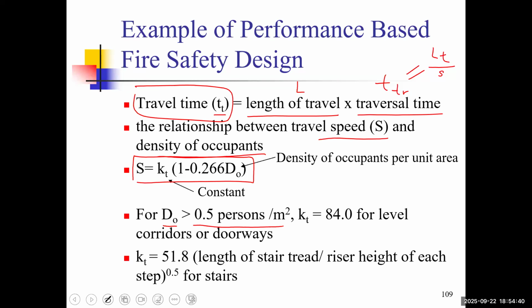And we have KT equal to 84 for level corridor or doorway. And KT will increase in value if we have length of stair, tread, and riser. Okay, we have the staircase, we have the tread and riser, which is different depending on the riser, which is vertical, the tread, which is the depth of the steps, for each step to the power 0.5 for the stairs. So we notice that there are different characteristics of the pathway.